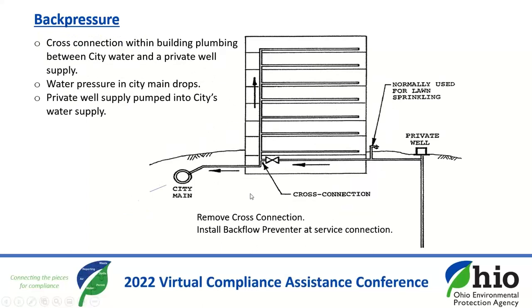This is an example of a backpressure condition. Here you have a city main supplying water to a building, but also a private well on the property supplying water for lawn irrigation. There is a cross-connection with just a shutoff valve separating the two. A backpressure condition can result if the city main's pressure drops, the private well pump overcomes the building pressure, and the private well supply backflows into the building plumbing as well as back into the public water supply. What we need is a physical separation and a backflow preventer installed at the service connection to prevent any backflow into the public water supply.